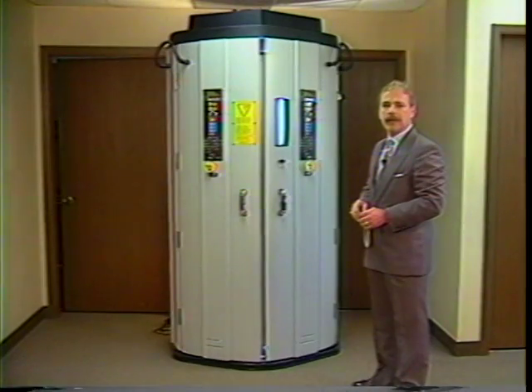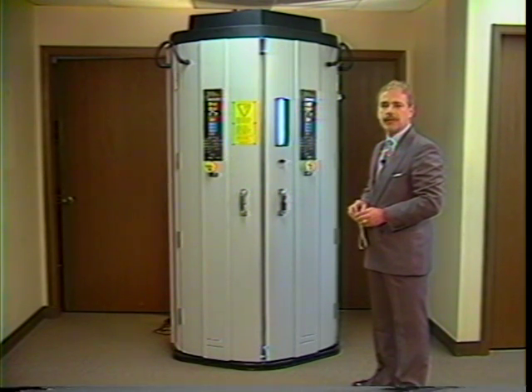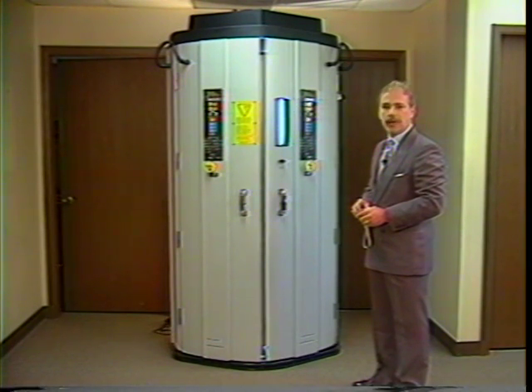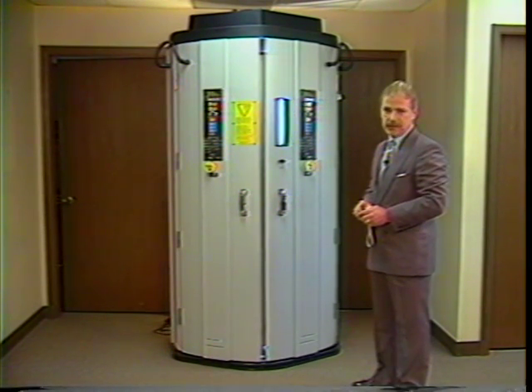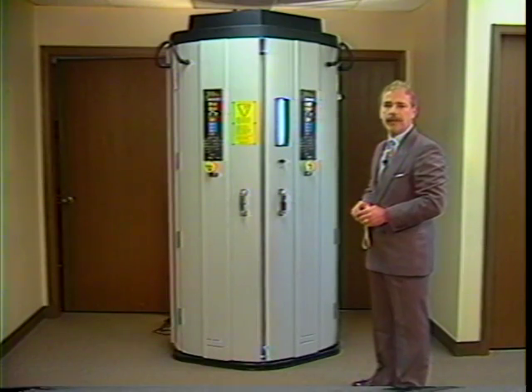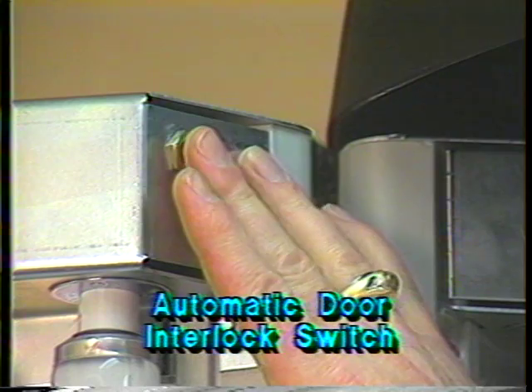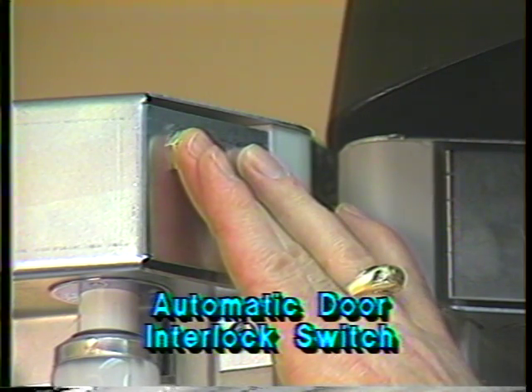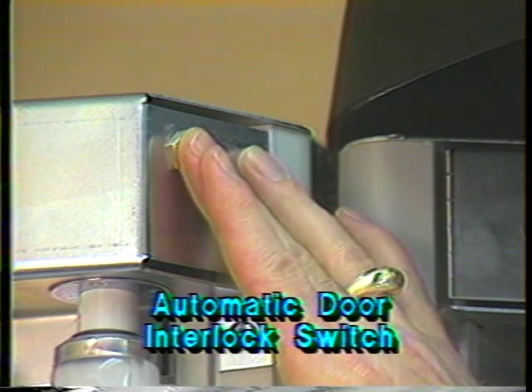The patient can exit the booth during treatment at any time, and the automatic interlock switch will shut off the lamps and the timers will stop counting down if the doors are opened further than 2 inches. This will prevent unnecessary UV exposure to the operator. The patient then re-enters the cabinet and closes the doors. The lamps and the timers automatically restart and treatment will resume.